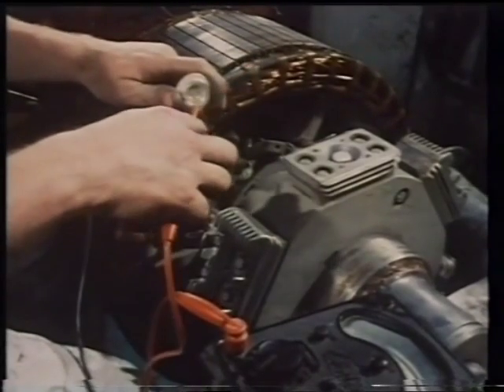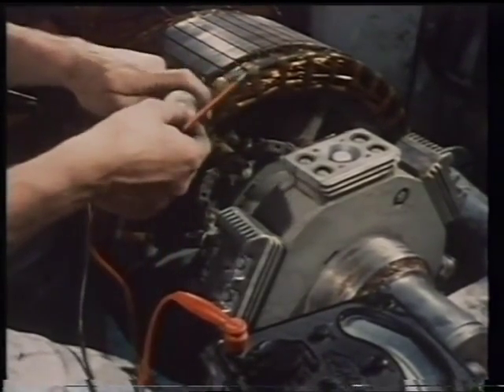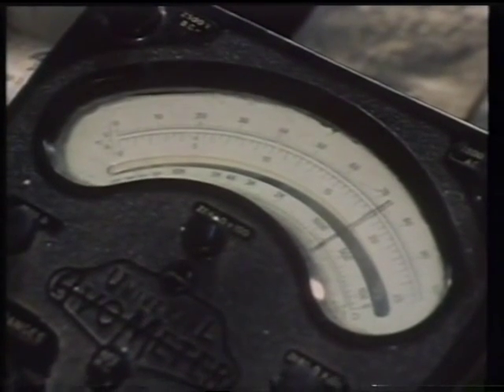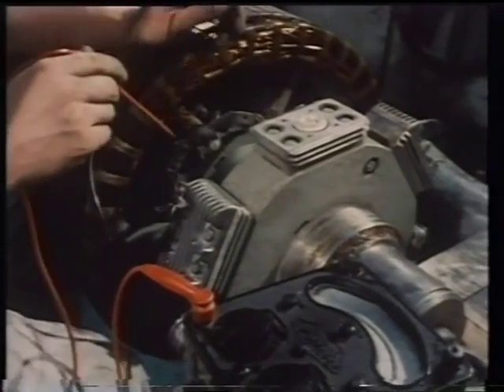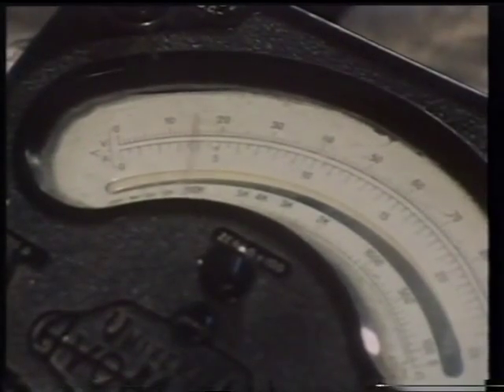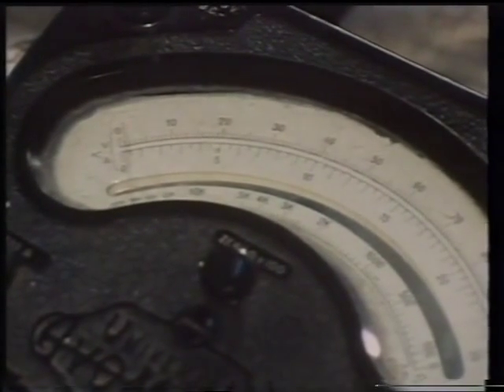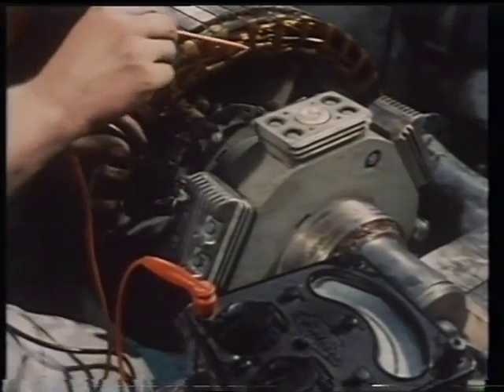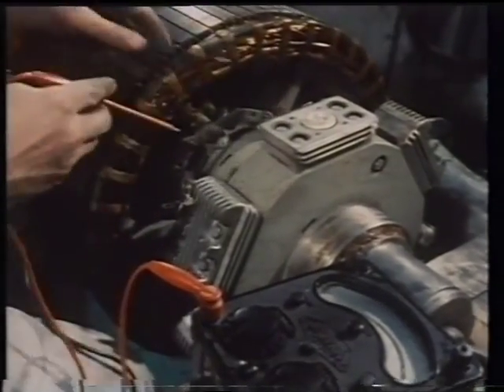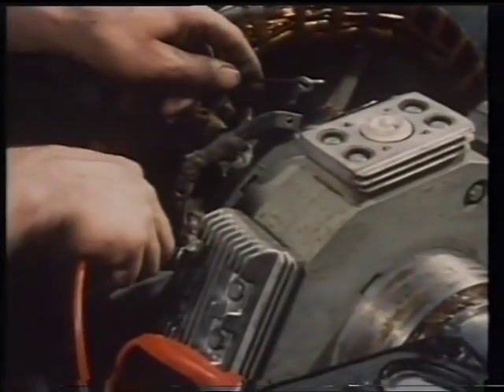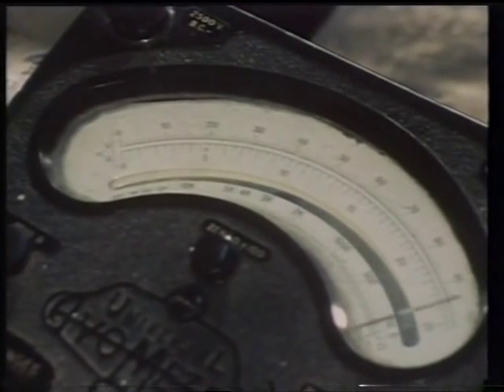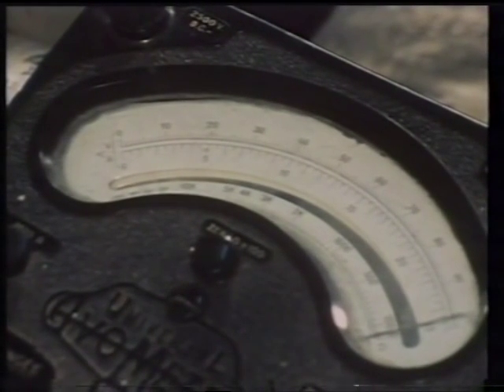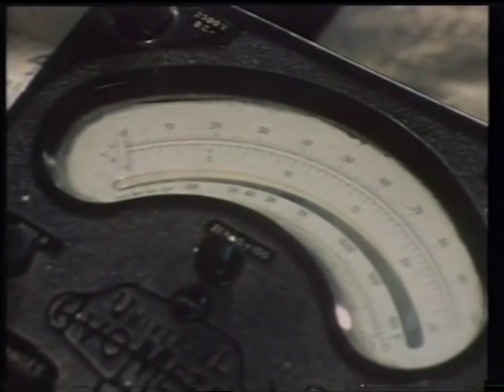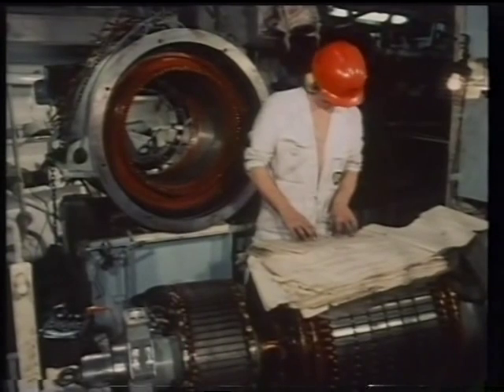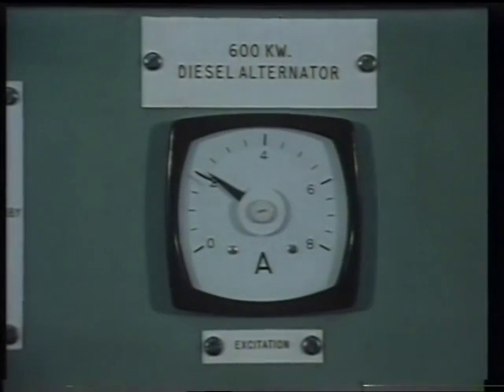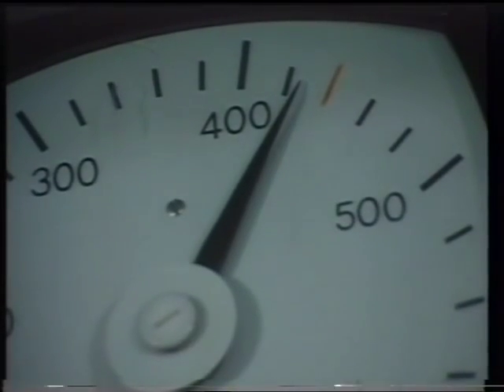Now measure the diodes in both directions. All diodes must be checked, but we show only one here. Then check the capacitor, which in this case is built into the rotating disc. The pointer shows that the capacitor charges up from the internal batteries of the meter. This indicates that the capacitor is all right. The test is done in both directions across the capacitor. Now the resistor. And there is the fault. The meter shows a short on the resistor. On this machine, the resistor is built into the rotor shaft, so that there's no question of a simple and quick repair. Reconnect and run the system without the resistor, but have it replaced as soon as possible.